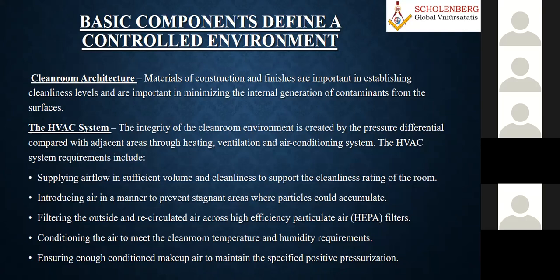Again, architecture is another important thing, because when you construct a clean room, it can range from a workstation, from a small room, to a very big area. As an example, again, I'm telling the process industry, they have about 25,000 square meter area. More than that, I'm not able to remember. But in that, the process area where the clean room is to be maintained is only about 1,000 or 2,000 square meters. Whereas as HVAC men, we misunderstood, and we started designing the whole area in a different condition. It involves so much capital cost and all these things. Later, when we discussed with the architectural and process consultant, it was clarified.